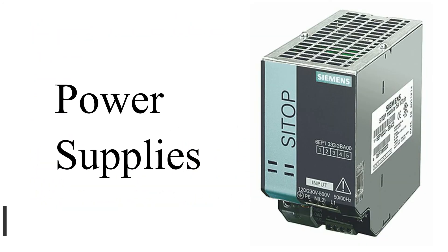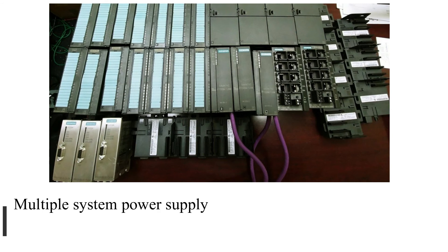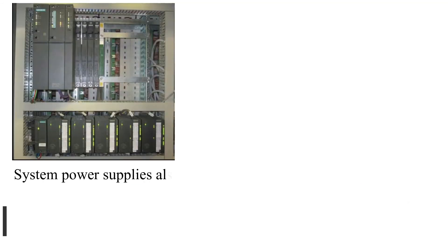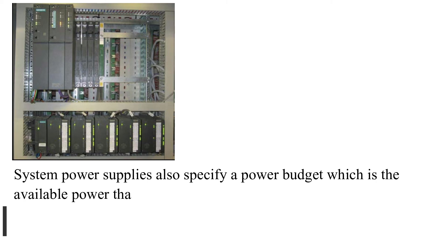Power Supplies: Multiple system power supply types are typically available for a PLC model to match the system voltage. System power supplies also specify a power budget, which is the available power that a supply can provide to interconnected modules.